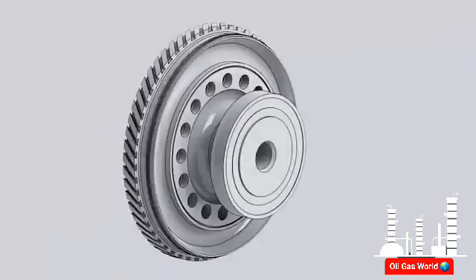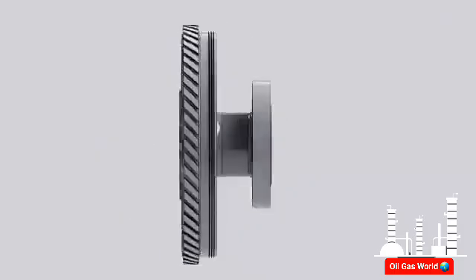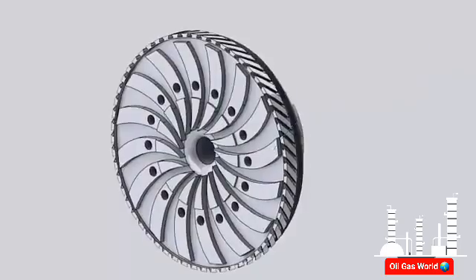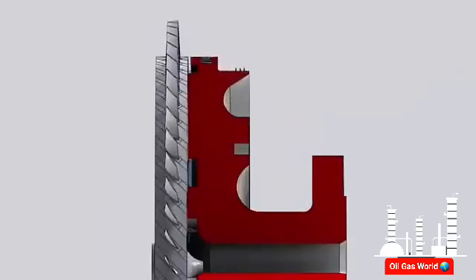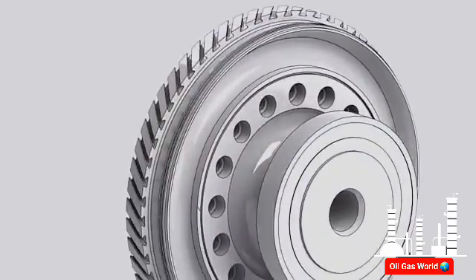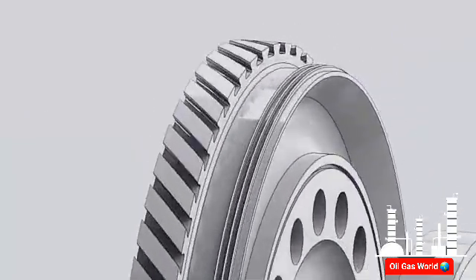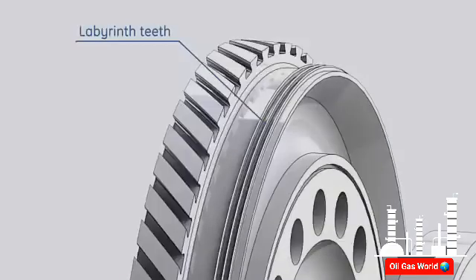The aft stub shaft is machined to provide the following features: a fan machined on the forward side of the stub shaft, which draws air through the gap between the 16th wheel and the aft stub shaft to cool the turbine rotor parts; an aft balancing groove; an aft flange to connect the compressor rotor to the turbine rotor; and labyrinth teeth to mate with compressor stator parts, preventing compressor discharge air from escaping inside the inner barrel around bearing number two.